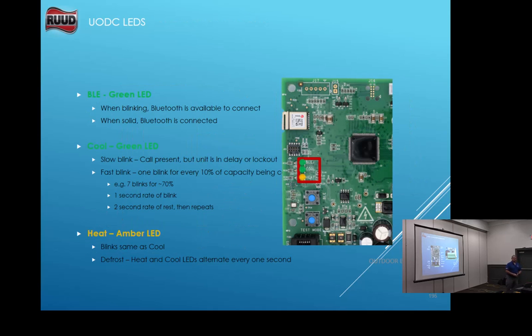On the outdoor units, on the boards, and the indoor, you have a BLE light right here. That's for our Bluetooth operation. If it's flashing, it tells you a Bluetooth connection is available. If you connect to it with your phone, it's going to go solid green. The other two, for cool and heat, flash once for every 10% capacity called for. So if it flashes seven times, you've got 70%. If it flashes 5 times, it's calling for 50%. Okay?